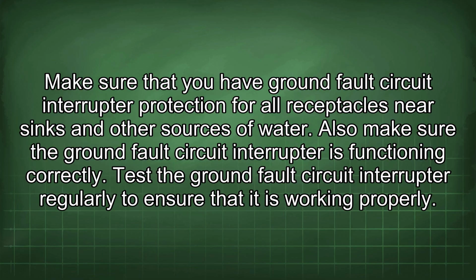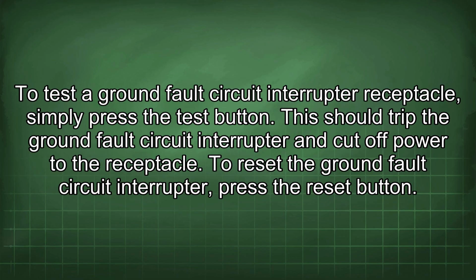Also make sure the ground fault circuit interrupter is functioning correctly. Test the ground fault circuit interrupter regularly to ensure that it is working properly. To test a ground fault circuit interrupter receptacle, simply press the test button. This should trip the ground fault circuit interrupter and cut off power to the receptacle. To reset the ground fault circuit interrupter, press the reset button.